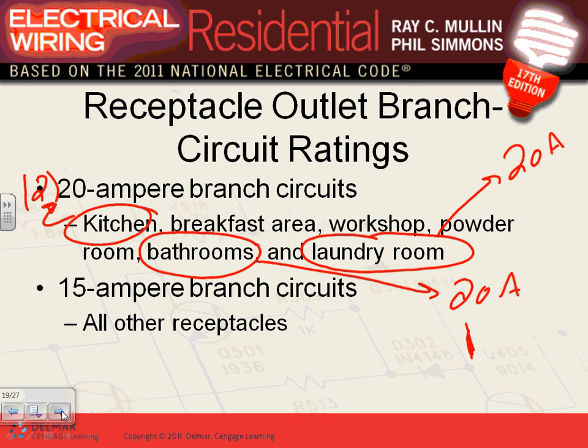I hate it when people act like angels. We've all done it. It's so easy. You have a receptacle right here, and they need a receptacle on the other side. Take that one out, drill through, move in. Well, oops, this wasn't a countertop receptacle. That's a violation if that receptacle was a countertop receptacle in the kitchen, anywhere in the kitchen or dining room, or if it was a laundry or bathroom. I call them the sacred cows.